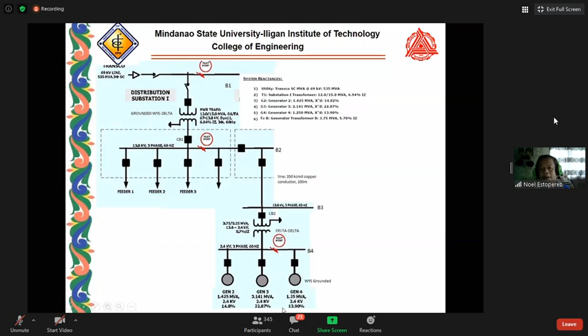Okay? So what happens here, our assumption is a system based on 15 MVA, transformer 1 at 69 kV. So we will analyze by per unit. Each quantity should be based on the 15 MVA at transformer 1, which is on the 69 kV side. So these are the representations. This is the equivalent representation of the utility, and the equivalent short circuit MVA, which was determined in terms of the utility impedance. These are also the generator reactances.